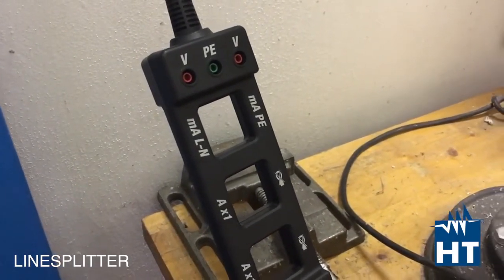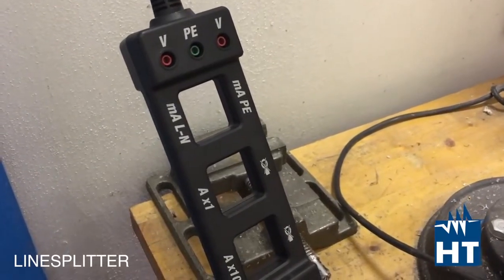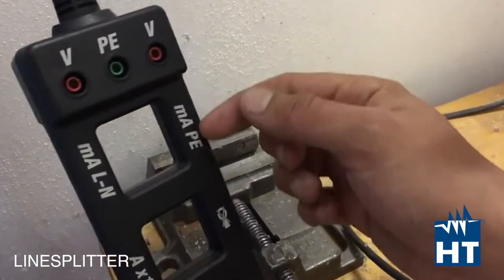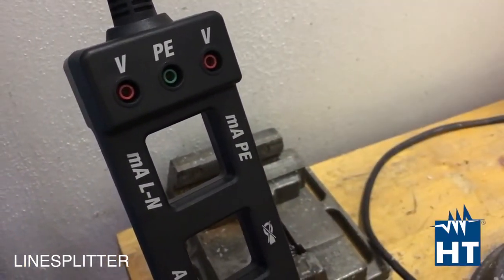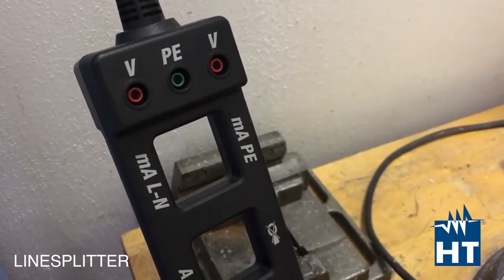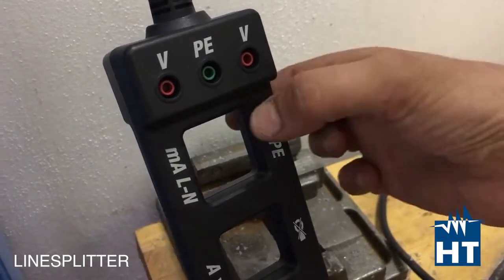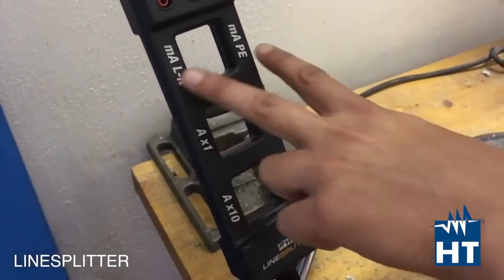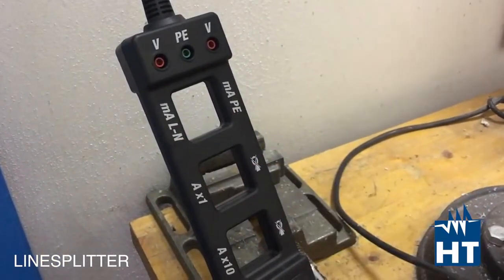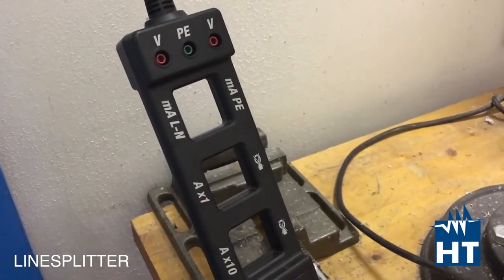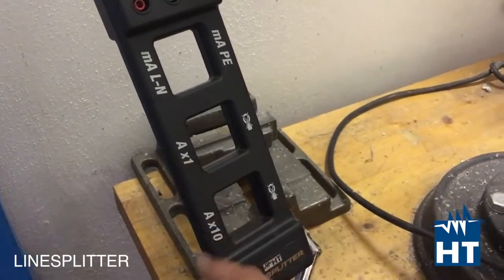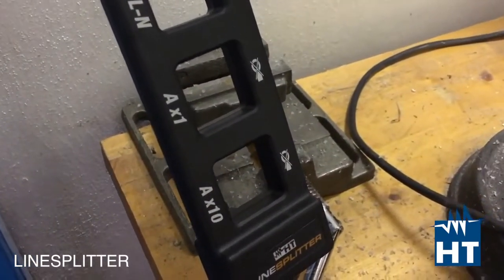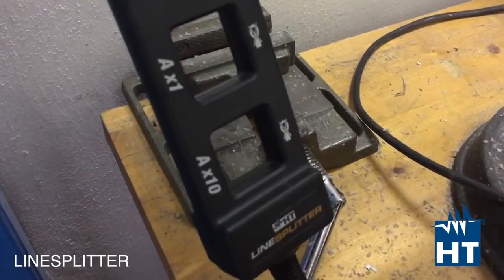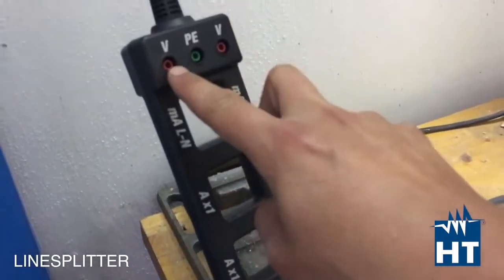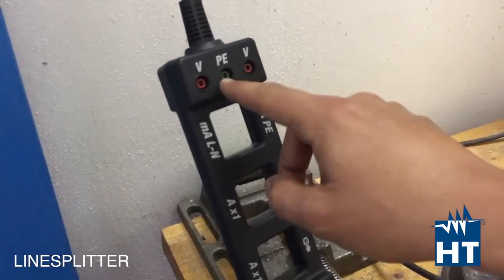If you don't have leakage, you should expect to read zero, because both magnetic fields cancel each other. From the other side, you have just the PE conductor, the protective earth conductor. If you have a leakage going through the PE conductor, you can measure it directly from this loop. So these two values are supposed to be the same. Otherwise you have leakage on the mass of the motor, so it can be very dangerous. Then you have a simple multiplier of current by 1 or by 10, so you can easily read the lower current with a normal current. And moreover, you have the voltage measurement between phase and neutral, and between the protective earth conductor and the phase or the neutral.